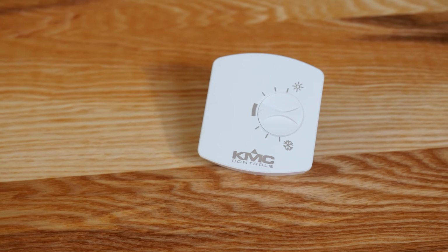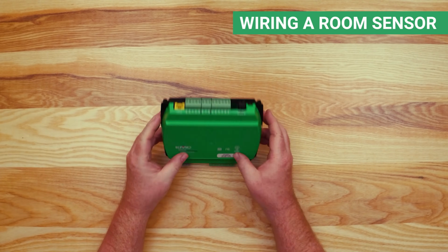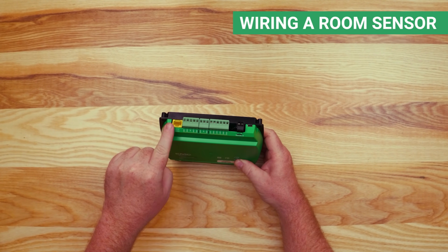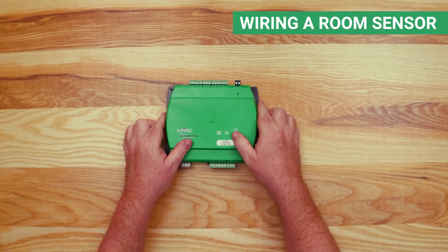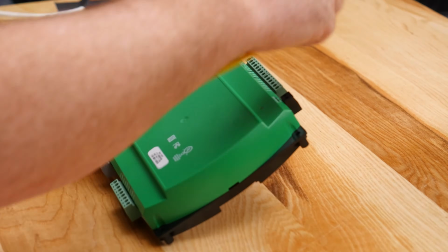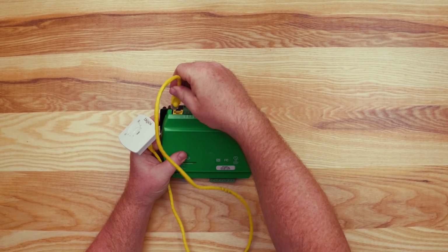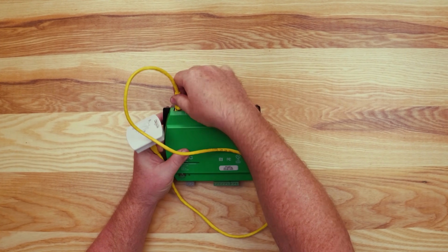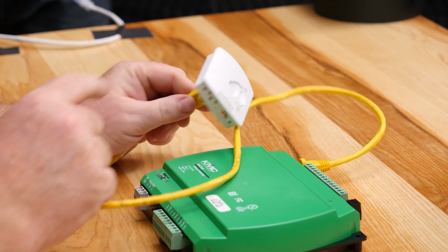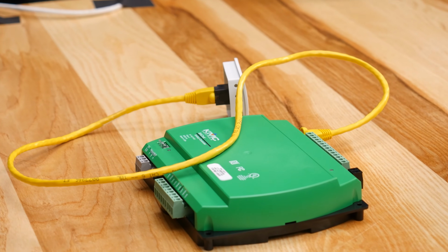If you'll be using one with your controller, another simple item to wire is the room sensor. Each controller in the BAC-9300 series has a yellow room sensor Ethernet port on the top of the controller. This port can be used to connect and add power to a KMC room sensor. Since this port is supplying power exclusively for the room sensor, please make sure you do not plug in a network connected cable. Doing so could cause damage to other hardware on the network.